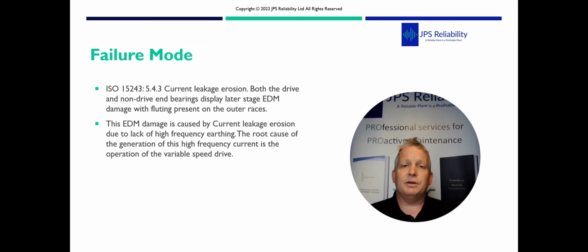So now we've seen the vibration data, we've seen the bearing images, we've physically seen the bearing. What's the failure mode? Well, you can say the failure mode is ISO 15243, 5.4.3: current leakage erosion due to the EDM damage. Now, is that the failure mode? Is that the root cause?